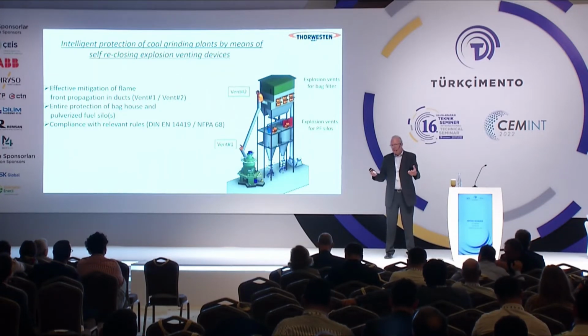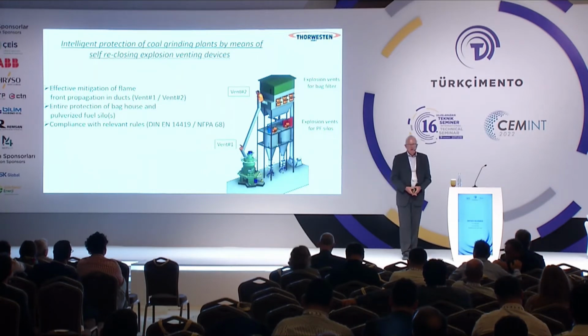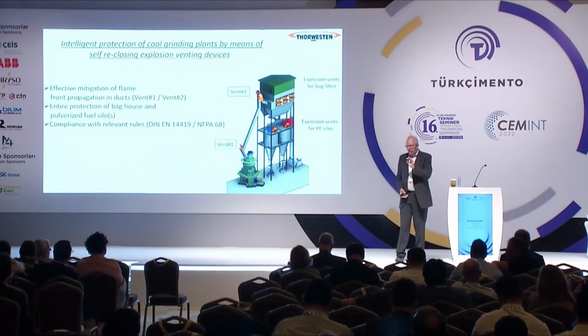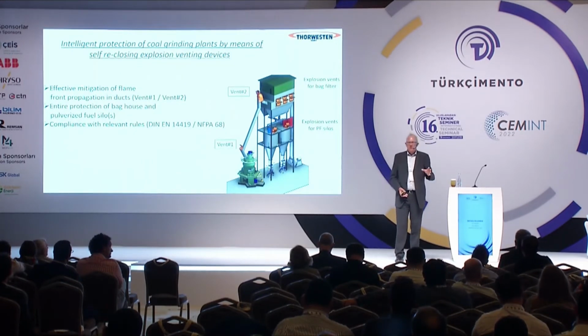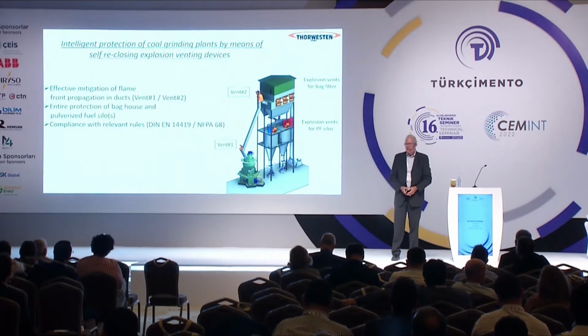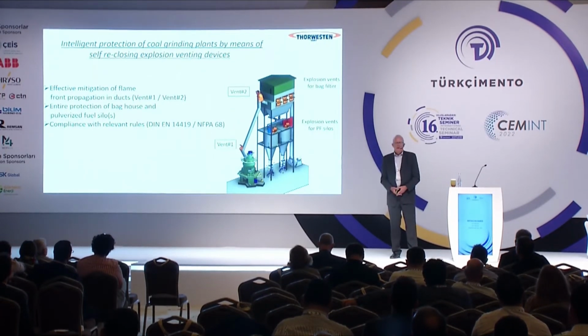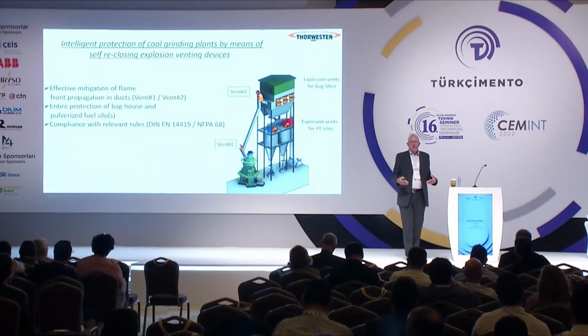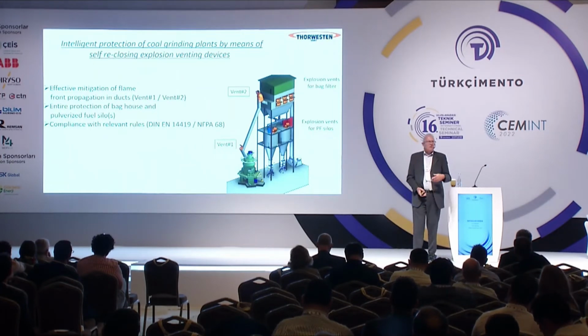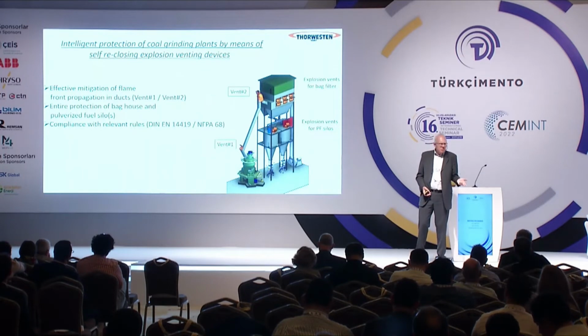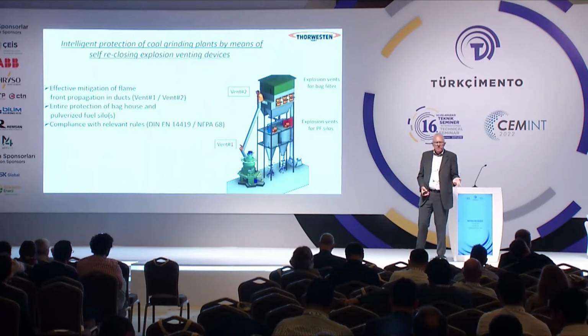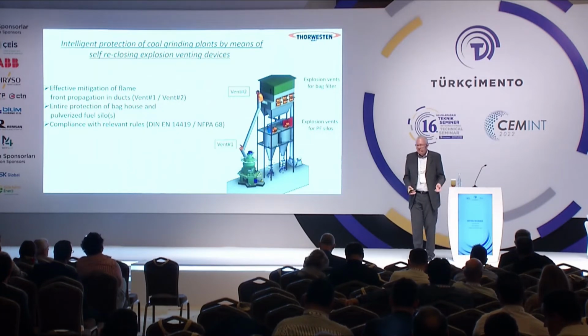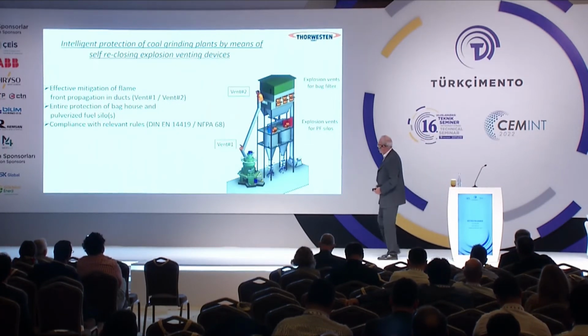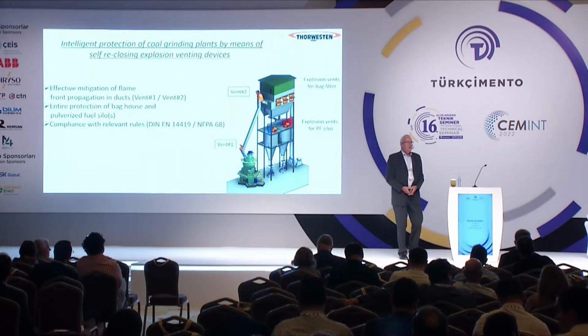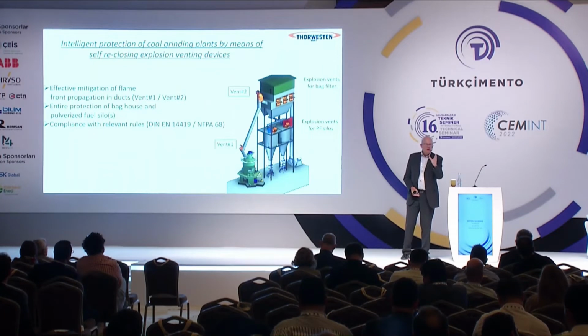You may remember that a coal dust explosion always comes along with a fire. Now the phenomenon starts that this pressure of 2 bar g created in the mill pushes the flame body into the riser duct. And the longer this riser duct is, the higher the velocity and the higher the pressure peaks at the end of this duct. That means everything connected at the end of this duct is going to be blown away, because it is exposed to such tremendous forces and pressure peaks it cannot withstand. It is blown apart. Therefore, the first venting device, called vent number 1, is very decisive with regard to getting rid of the explosion pressure created in the mill body.